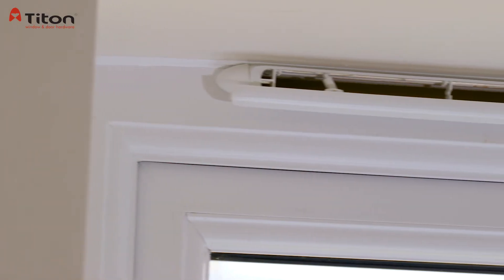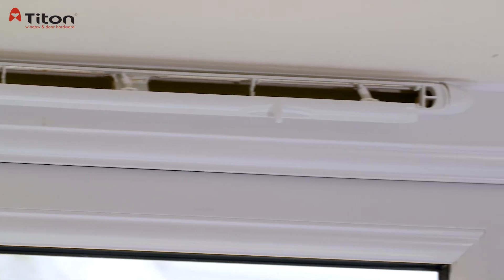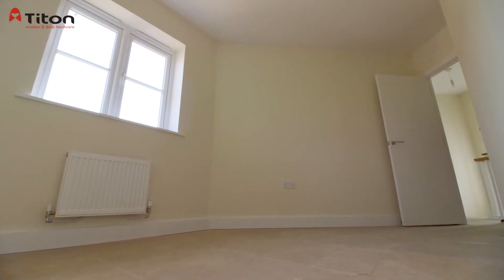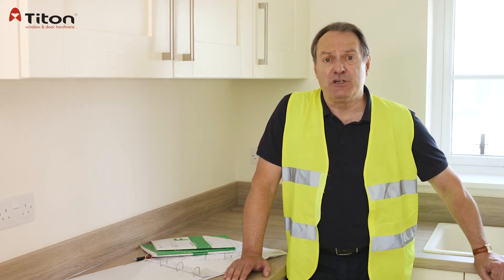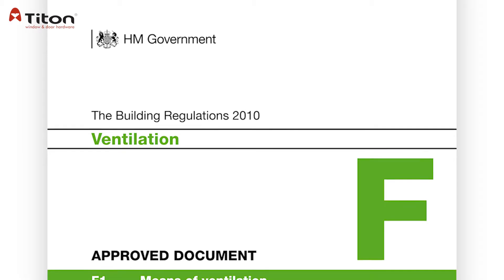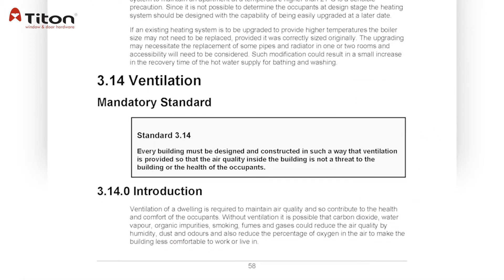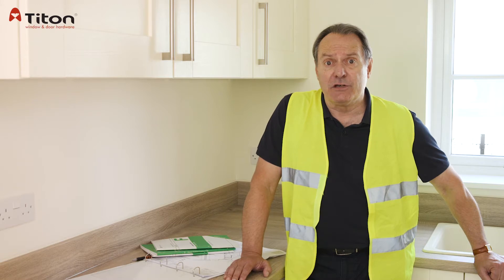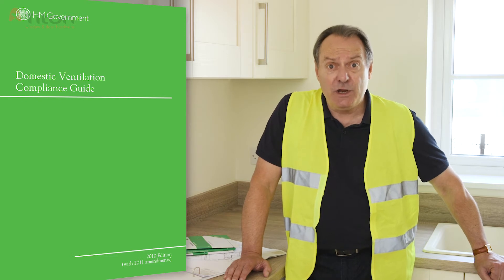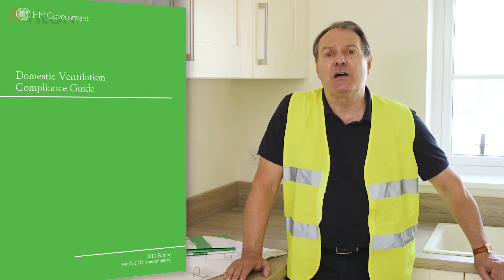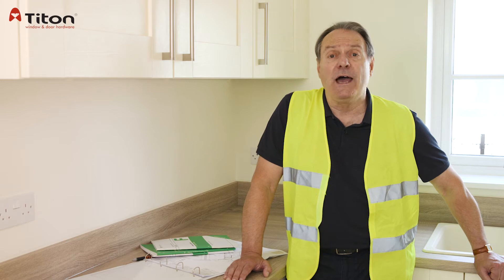The quantity and size of the vents required depends on a few factors. Whereas traditionally the property used to comply with two vents in each habitable room and one in each non-habitable kitchen or bathroom, anyone approving the property's ventilation compliance now needs to closely reference Approved Document F for England and Wales, or the Technical Standards for Scotland. There is also a document called the Domestic Ventilation Compliance Guide, or DVCG, which is an aide-mémoire for this purpose and provides sign-off forms for contractors relevant to all ventilation system types, including whole house systems.